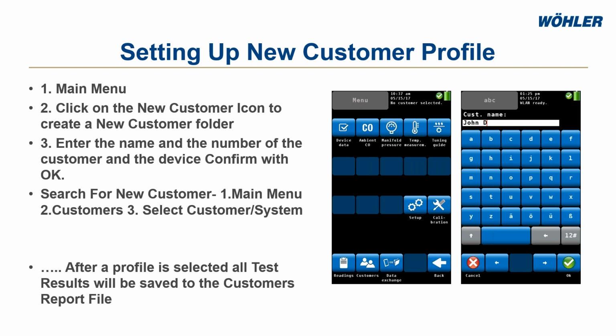So here's an example of setting up a new customer profile. A lot of people don't realize that the A450 has this feature. The A450 has the capability to create custom profiles within the analyzer. This is really important because if you have several hundred different customers and they all have service contracts with you and you go out and see them every year, you need a way to compare results from last year to this year. By creating a customer profile within the analyzer, it allows you to reference data or go back whenever you need to and print out results, or use the app to send emails of the customer's readings.